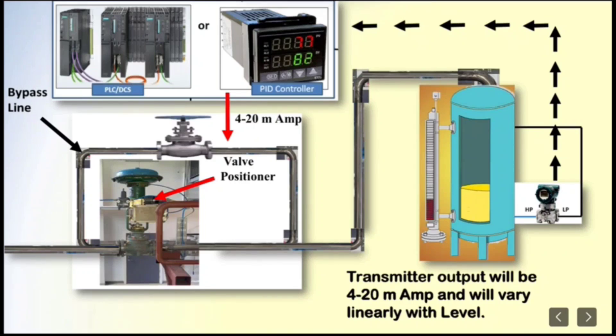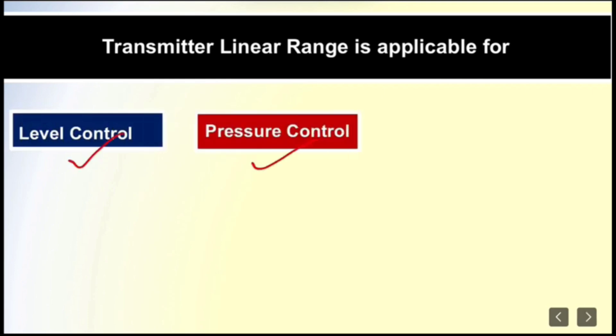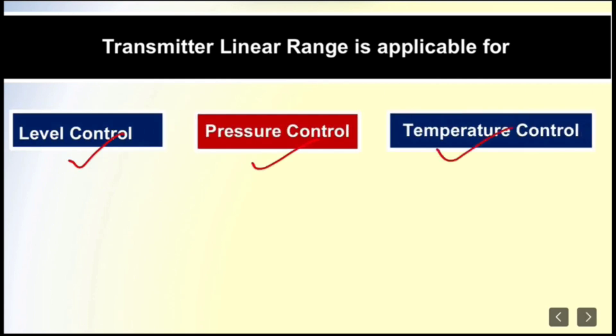It is also important to know where the transmitter linear range is applicable. It is applicable for level control, pressure control, and temperature control. For flow control, we use square root range.